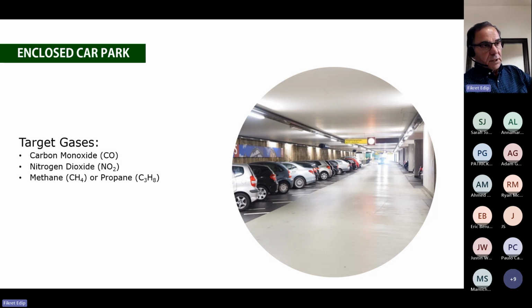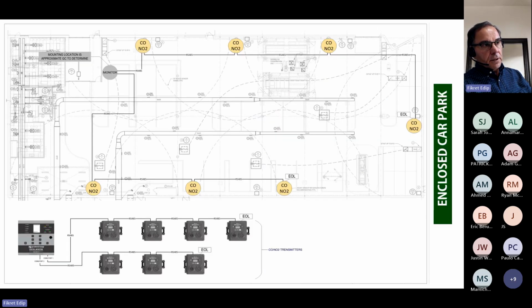In some provinces, like BC, they are still using propane gas for underground parking. And here it gives you a typical layout for underground parking, where we allocate our sensors depending on the size of the area, which I just said regarding where I should be locating my sensors. In the system, you have several sensors connected to a controller, typically mounted somewhere here in a mechanical room, to activate fans and all that.